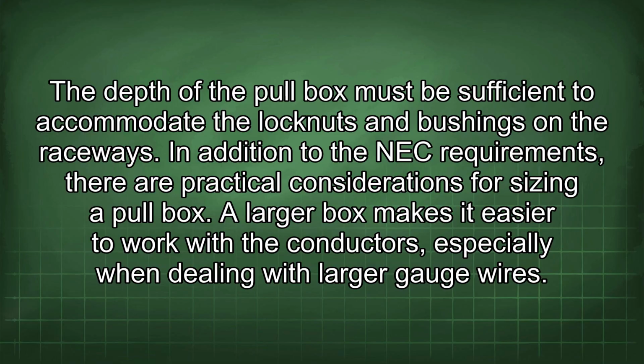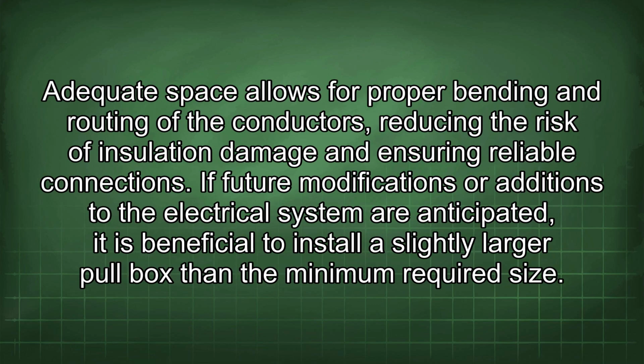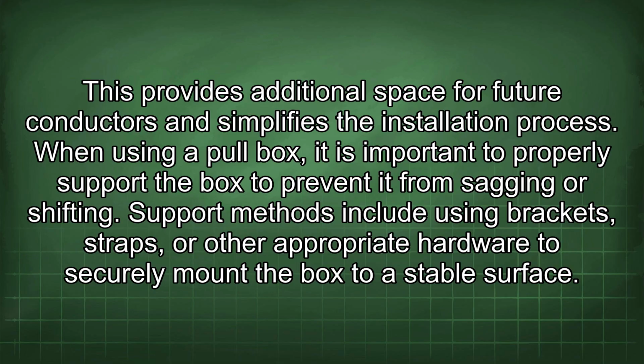In addition to the NEC requirements, there are practical considerations for sizing a pull box. A larger box makes it easier to work with the conductors, especially when dealing with larger gauge wires. Adequate space allows for proper bending and routing of the conductors, reducing the risk of insulation damage and ensuring reliable connections. If future modifications or additions to the electrical system are anticipated, it is beneficial to install a slightly larger pull box than the minimum required size. This provides additional space for future conductors and simplifies the installation process.